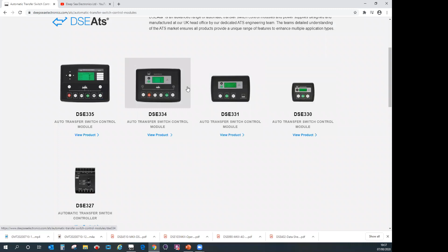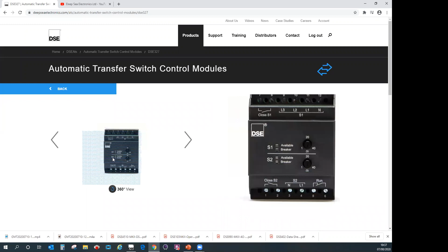And again, it's a variation on the same theme, but as you go down the range, you get less and less functionality. You lose your buttons, etc., and you end up with the 327, which is not configurable by configuration suite. It's just a very basic supply 1, supply 2. When supply 1 becomes unavailable, it will switch to supply 2, and it will just basically send out a command to open and close breakers.